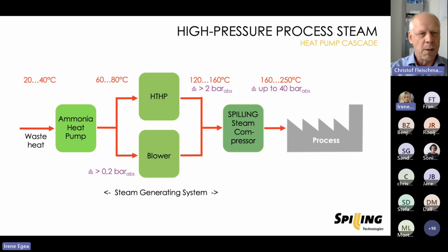Okay, this complete cascade, like it's shown here, was not often realized, or honestly speaking, I don't know installation where this complete cascade starting from 20-40 degrees Celsius as source side and on the sink side high pressure steam was so far realized. But we have some feasibility or some projects which are in the feasibility study phase. One project, for example, where river water shall be used as heat source in the US, and on the sink side, 6 bar steam shall be supplied for a district heating system.